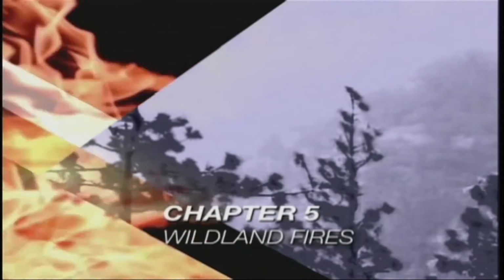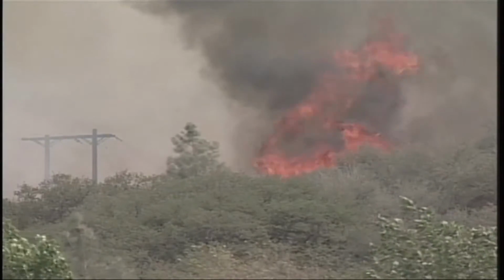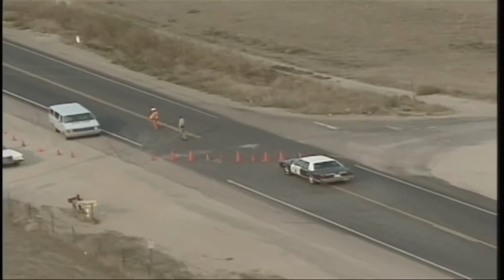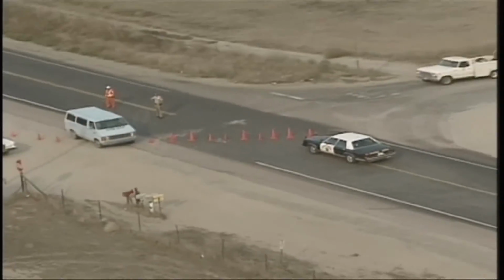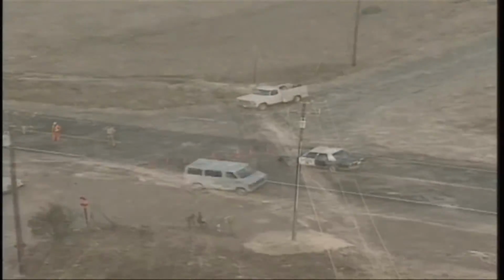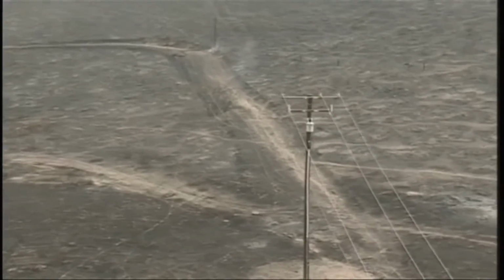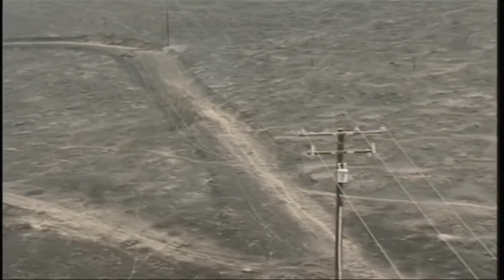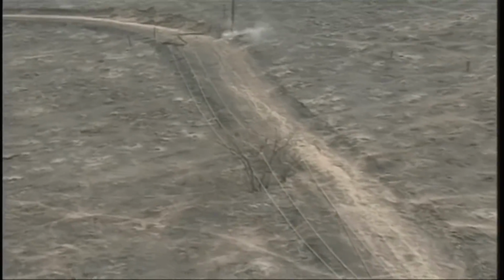Wildland fires can occur in many parts of this region. The most important thing to remember is to maintain a safe distance from the power lines, 1.5 times the height of the power line structure. Restrict public access outside that safe approach area. Do not consider cleared areas around Edison towers or poles as a safe haven during a wildland fire just because they are relatively free from vegetation.